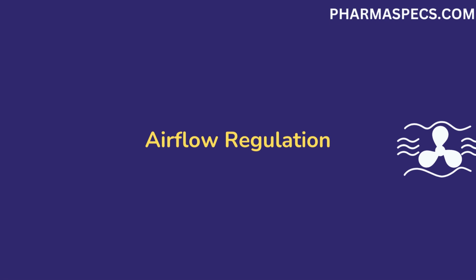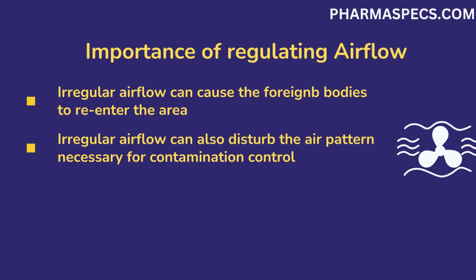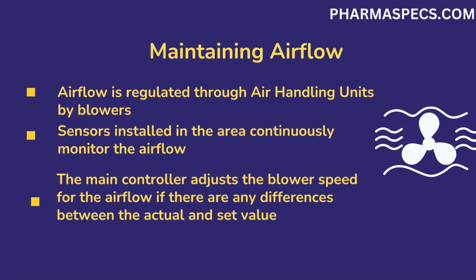Airflow regulation. Controlling airflow is also a critical parameter for pharma environment. If airflow is not regulated, it can disturb other related environmental parameters such as temperature and humidity. Irregular airflow can cause foreign bodies to enter in the area, resulting in contamination. It can also disturb the airflow pattern inside an area, which in turn also disturbs other environmental parameters such as temperature and humidity. Air handling unit is used to regulate the airflow.